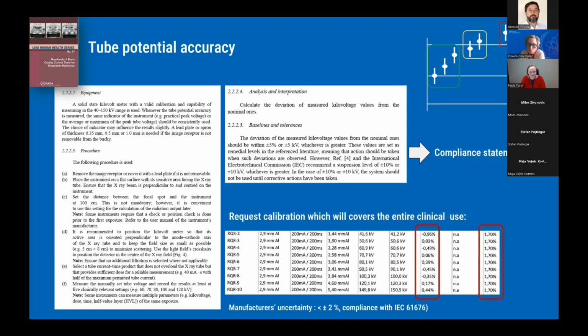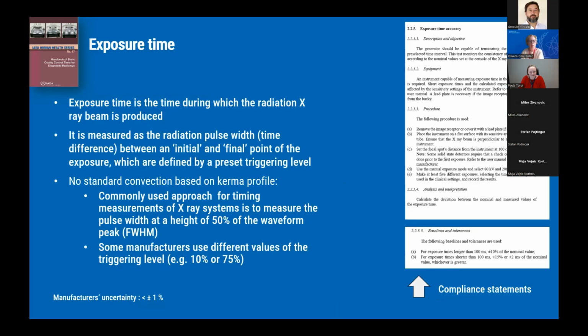Most of the manufacturers would also state compliance with IEC 61676 and practical peak voltage, though we have seen from the Miloš presentation that practical peak voltage is not extensively used in the clinical community. Similarly to tube voltage, exposure time is a parameter that is part of the quality control test. And we also learned from Miloš that there is no standard convention on how to define exposure time based on the Kerma profile. In most cases, it would be the distance between 50% of the waveform peak. However, some manufacturers would use a different convention and go for 10 or 75%.